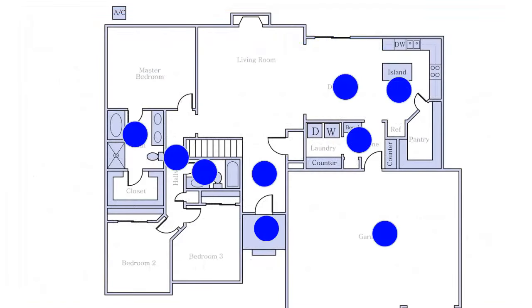Let's look at our drawing. Everything colored in blue is an area where you're required to have a light fixture that's controlled by a switch. Everything colored in red are areas where you would be allowed to use a switched receptacle. As far as wall switches go, we can use occupancy sensor switches instead of a switch as long as the sensor is a switch and it's in the location that a normal switch would be in. You can't just put an occupancy sensor in without a switch in those rooms.